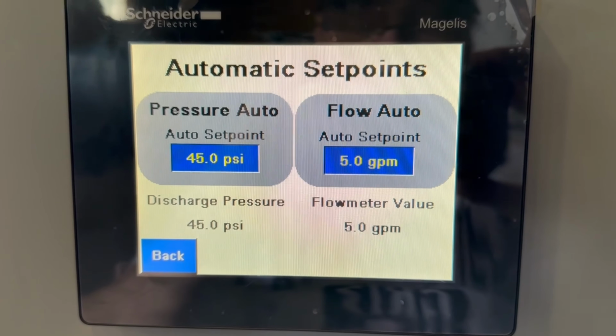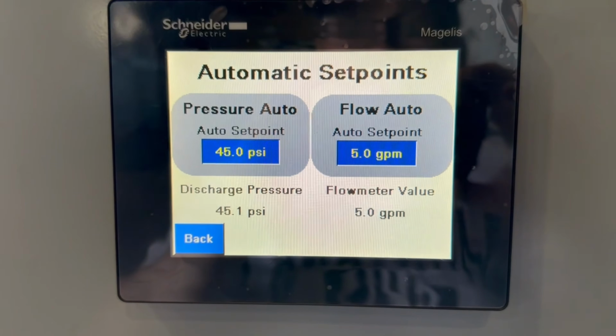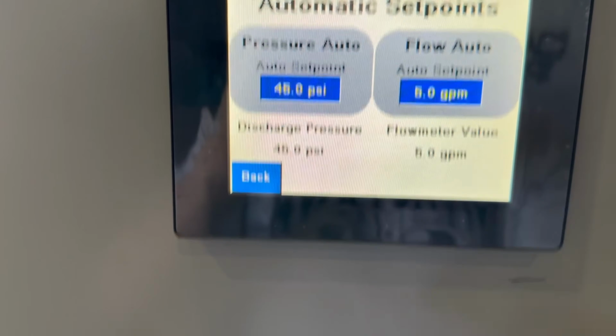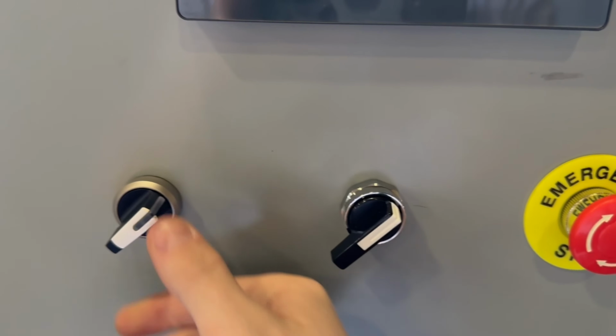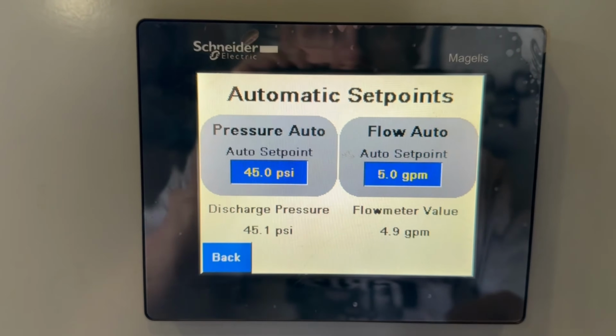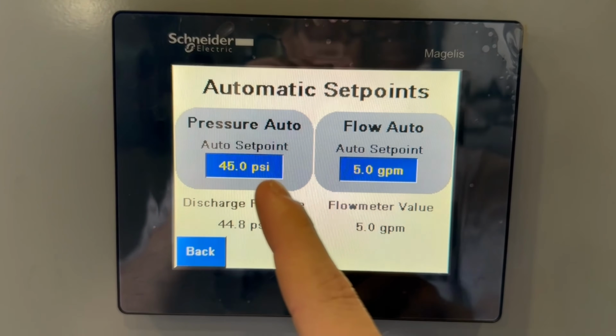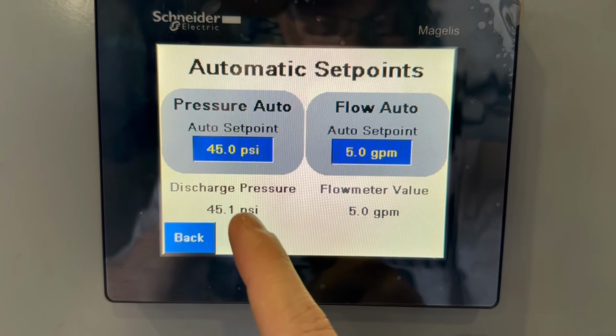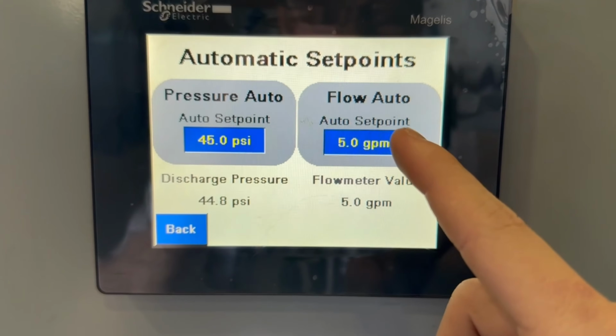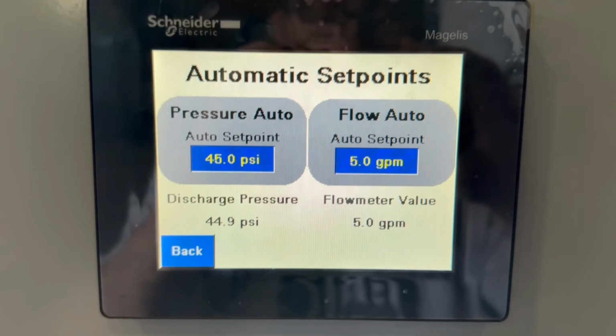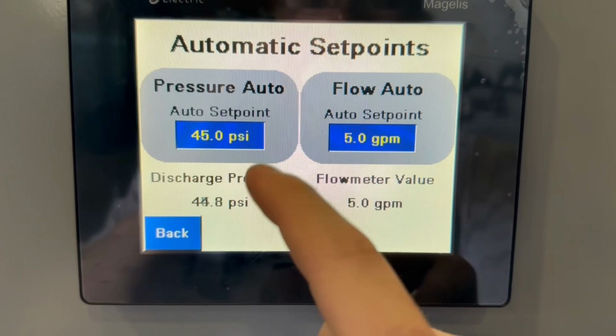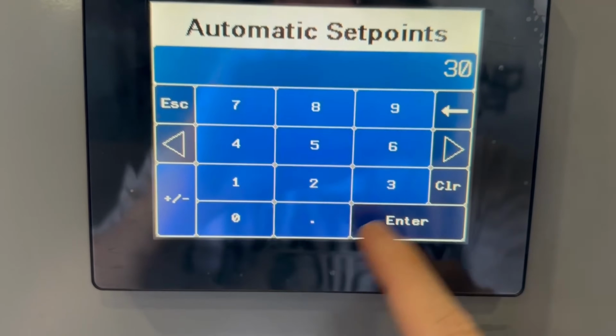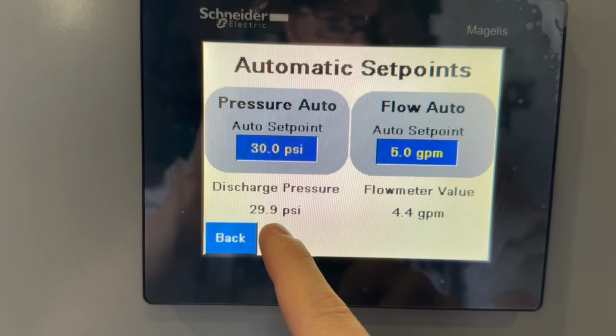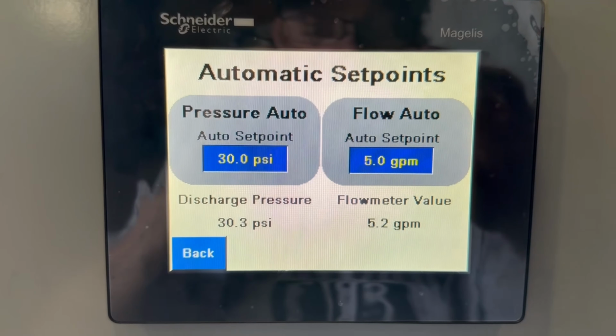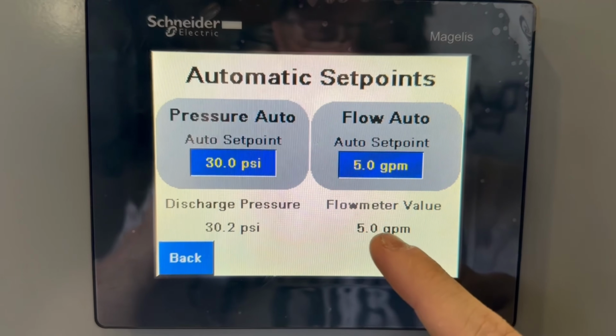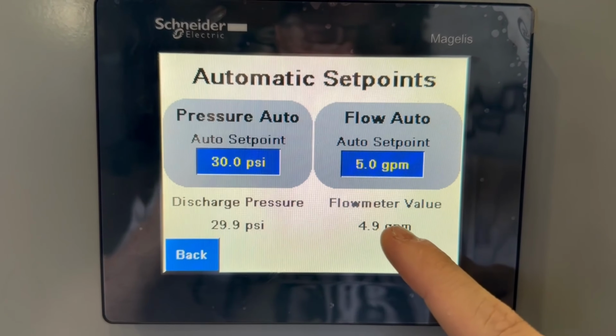So for this demonstration, I will be showing my PID settings. So for the automatic set points here, as we are in pump auto and valve auto mode, we can see here that the pressure is set to 45 psi, and we are maintaining that pretty well. And the flow is set to 5 gallons a minute, and we are maintaining that perfectly. So if I wanted to set this to 30 psi, the frequency on the pump will drop until that reaches 30 psi, and the valve will catch up slowly to get back to that 5 gallons per minute.